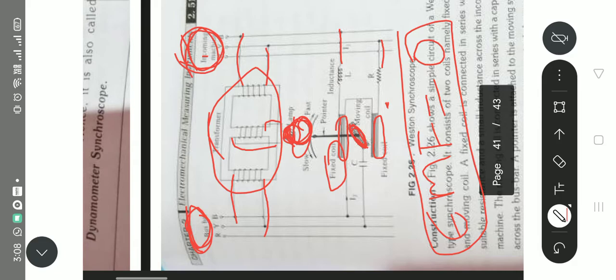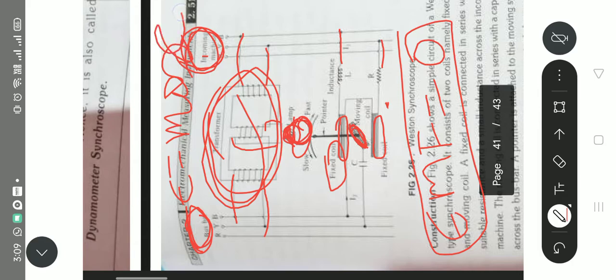To avoid that condition, we use this Weston synchroscope. When the bus bar voltage and incoming machine voltage are in phase, the EMF produced in the transformer is maximum, so the lamp will be very bright.